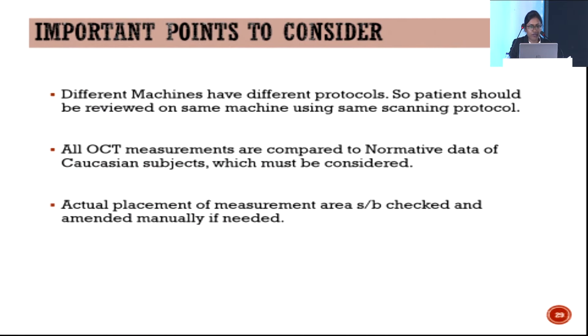Important technical considerations: different machines have different protocols, so patients should be reviewed on the same machine using the same scanning protocol. All OCT measurements are compared to normative data derived from Caucasian subjects, which must be considered. Actual placement of the measurement area should be checked and amended manually — segmentation must be correct in order to properly analyze the report.